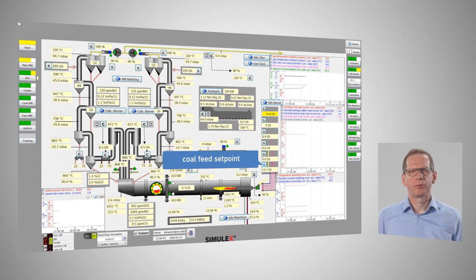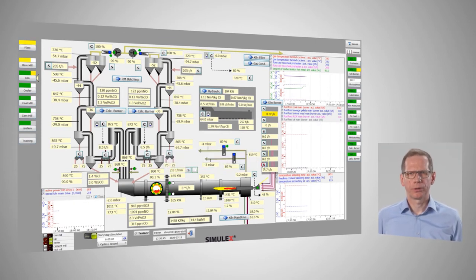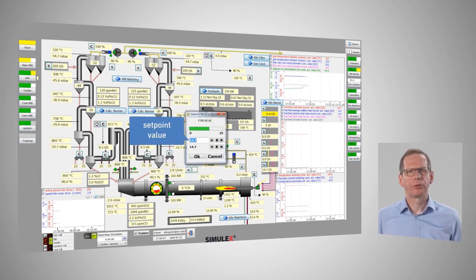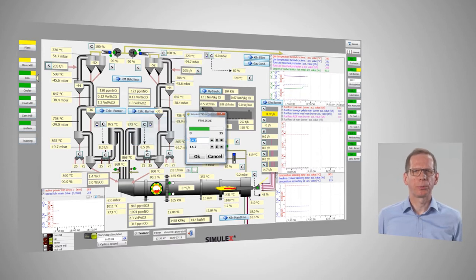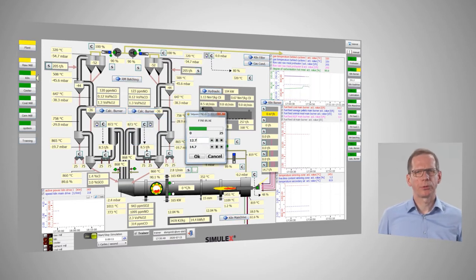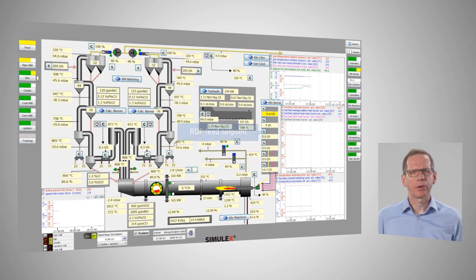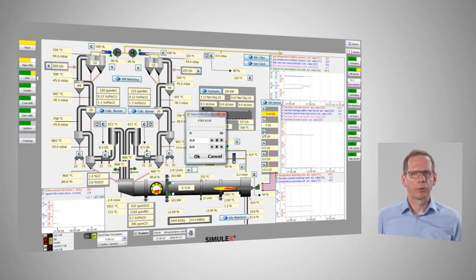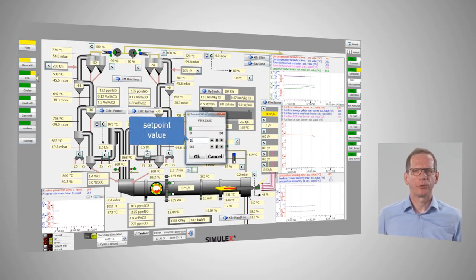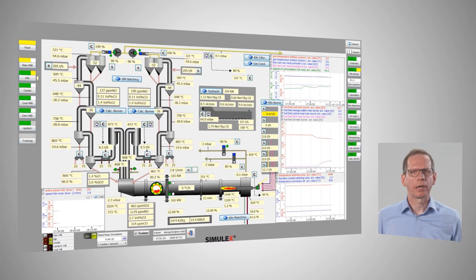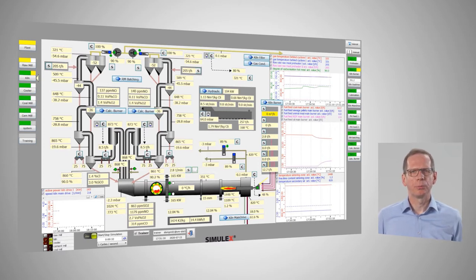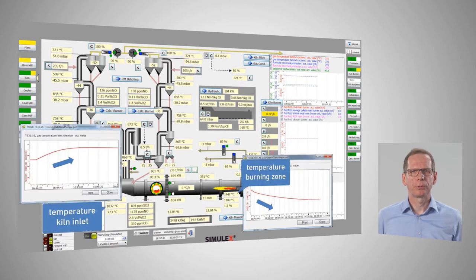That is what we will now do with different fuel types. We now want to adapt the fuel composition in our example scenario. First we will reduce the coal supply by 2 tonnes per hour. Next we will substitute this by an increase of RDF by 2.9 tonnes per hour — we need to fire more RDF to balance the required heat intake. As you can see, immediately after changing a value, our simulation scenario adapts in a similar way as your production parameters would do under realistic conditions.